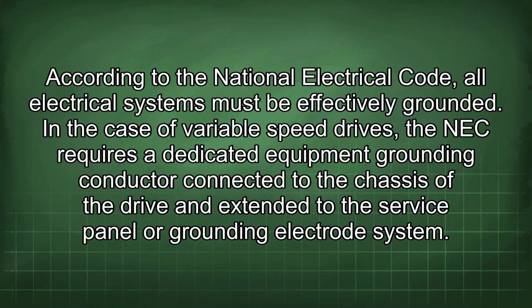According to the National Electrical Code, all electrical systems must be effectively grounded. In the case of variable speed drives, the NEC requires a dedicated equipment grounding conductor connected to the chassis of the drive and extended to the service panel or grounding electrode system.